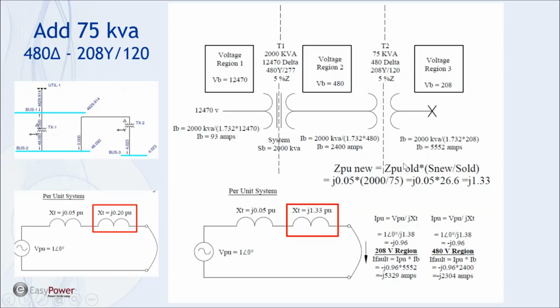You have three regions of your per unit system, and on the right hand side you show your current on the base as 5552, and at the bottom when you go to utilize the number, we're still calculating the 480 volt region fault current. You mean down here in the 480, where it says, well, this is the fault current in the 480 volt region. So that's going to be in region 2. Does that make sense? I think it does. This 5329 results in a fault current in the 480 volt region of 2304. Okay, that's what that means. Yeah, I think that's what I misunderstood. All right. Thank you.